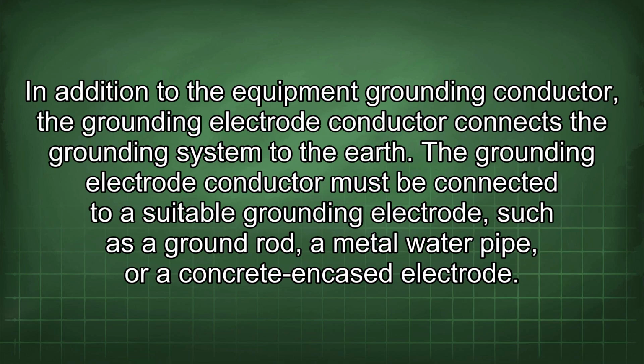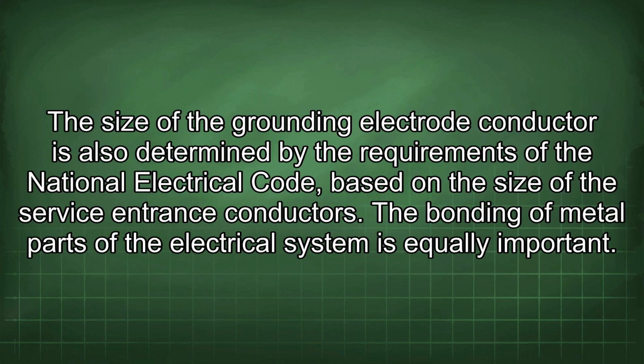boxes. In addition to the equipment grounding conductor, the grounding electrode conductor connects the grounding system to the earth. The grounding electrode conductor must be connected to a suitable grounding electrode, such as a ground rod, a metal water pipe, or a concrete encased electrode. The size of the grounding electrode conductor is also determined by the requirements of the National Electrical Code, based on the size of the service entrance conductors.